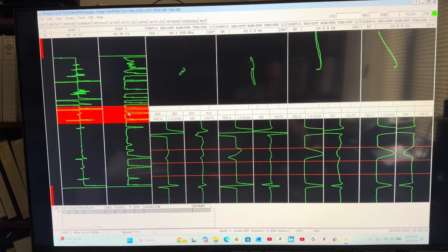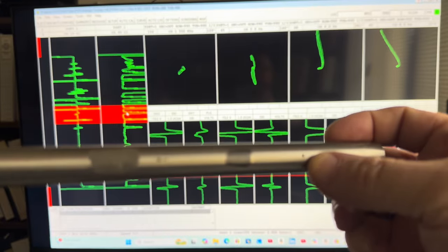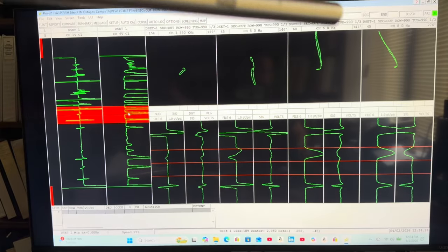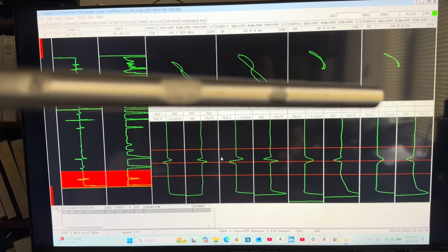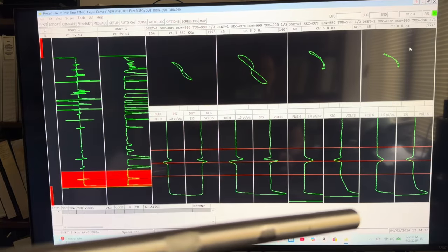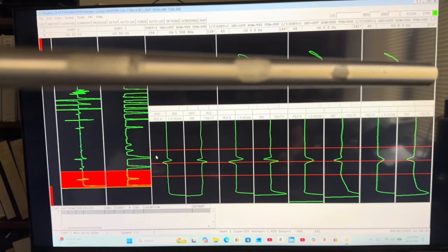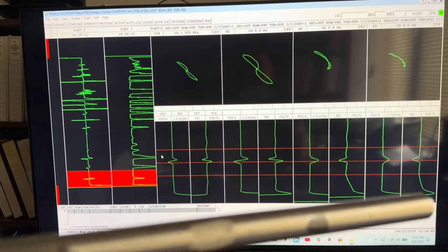So, just starting off, I drilled a small hole similar to the size hole that's in an ASME cal tube. And that's what shows up at the bottom of your screen here. Notice how I calibrated it on a couple different differential channels. 100% hole at 40 degrees. And then I got a couple absolute channels over here. And then the next thing there, I think that's just some sort of polishing wheel, which obviously didn't introduce any sort of flaw. There's nothing there.